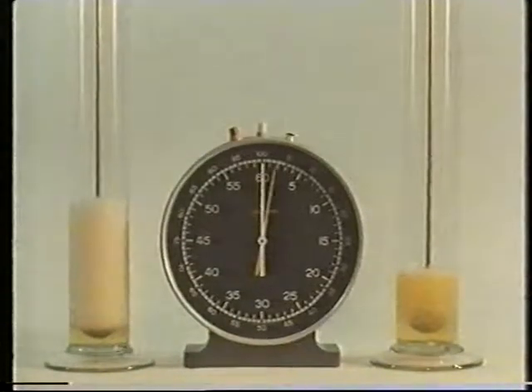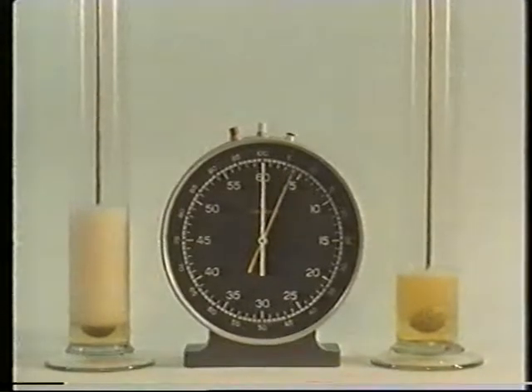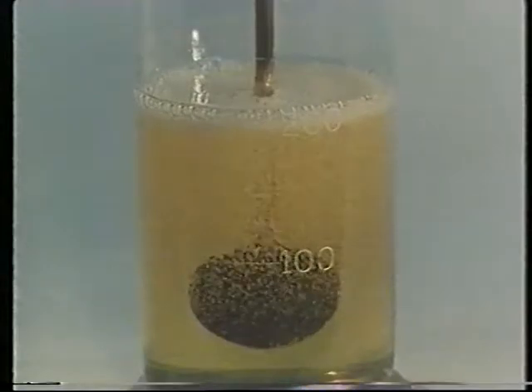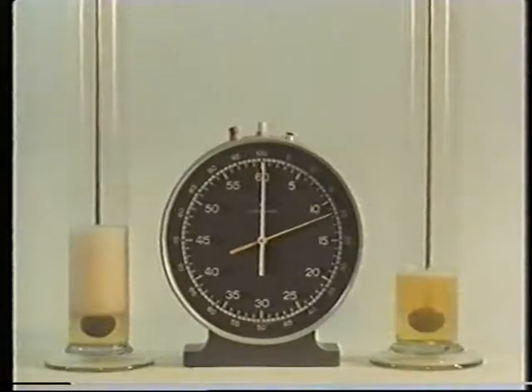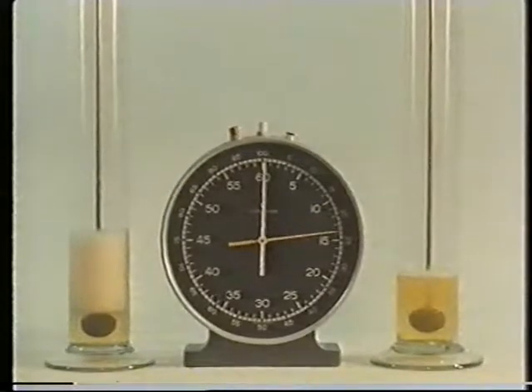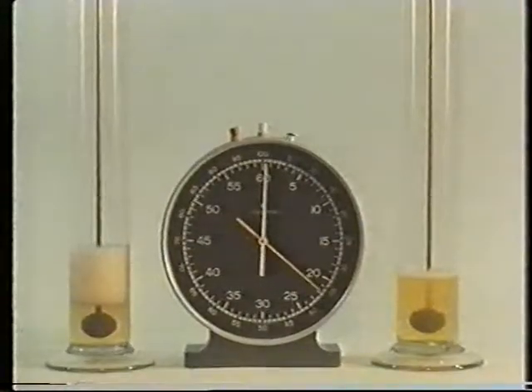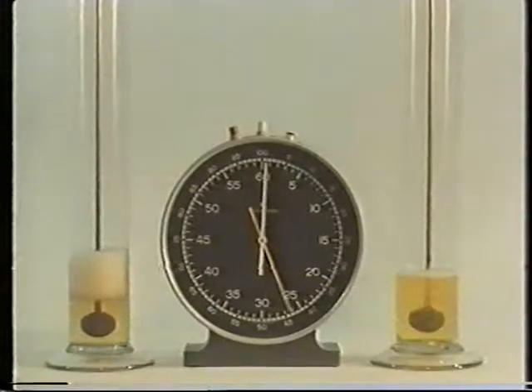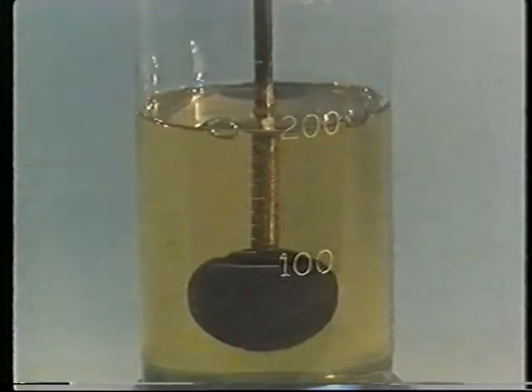An anti-foam additive is used in most hydraulic oils, as on the right. This test measures the difference in foaming. But additive treatment is very critical. The oil should not be overdosed, or air release will be retarded. In a properly designed and operated system, there would be no entrained air to cause foam.